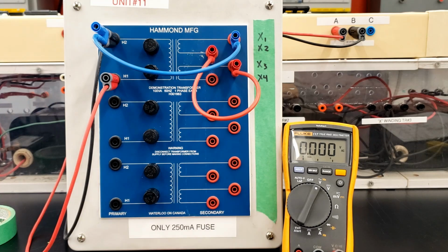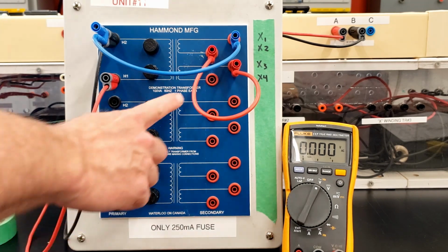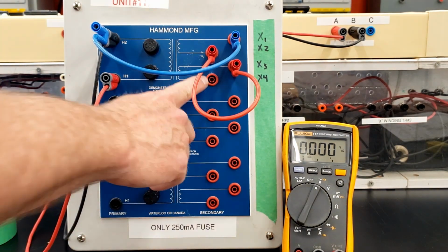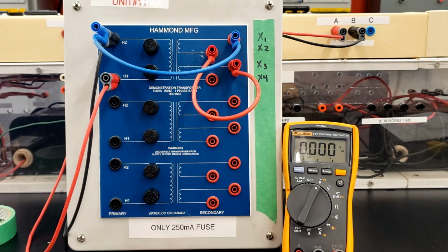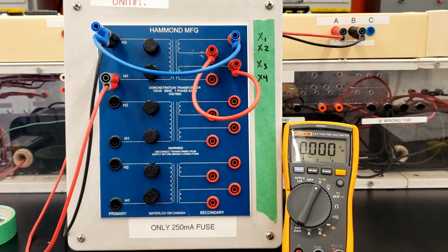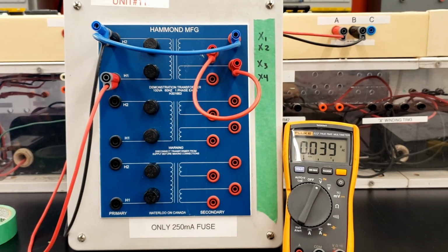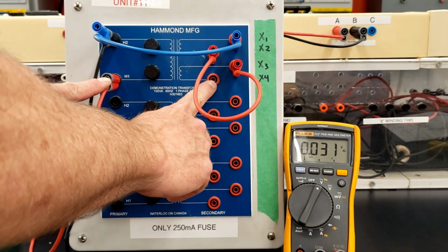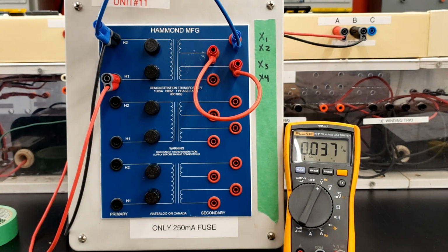When I power it up, I'm going to take the voltage between the two open terminals. One terminal that's open is right here, and the other open terminal is H1. So I'll be taking a voltage reading between H1 and X4. Just to be clear, I'm not shorting out the transformer here — I have two open connections, so I've created a series connection between primary and secondary, but I haven't short-circuited the whole transformer.